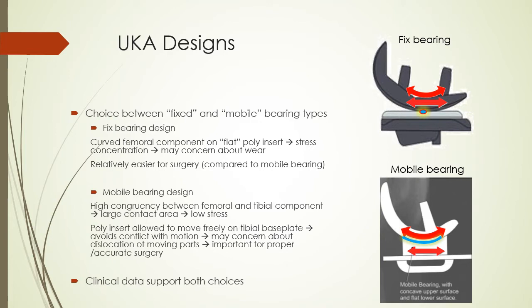But with the current poly materials, we have a much better material compared to back then to minimize poly wear. And because it's a flat surface, fixed bearing, it's very easy to do the surgery compared to a mobile bearing design. So the reproducibility of the surgery is pretty good.